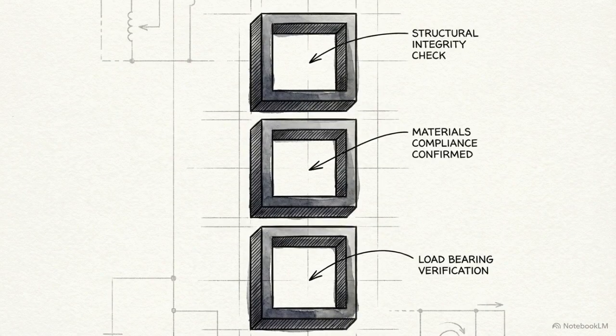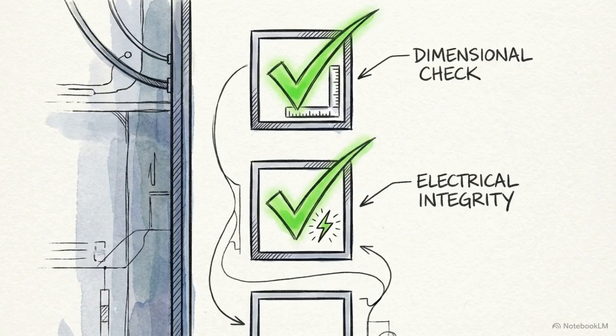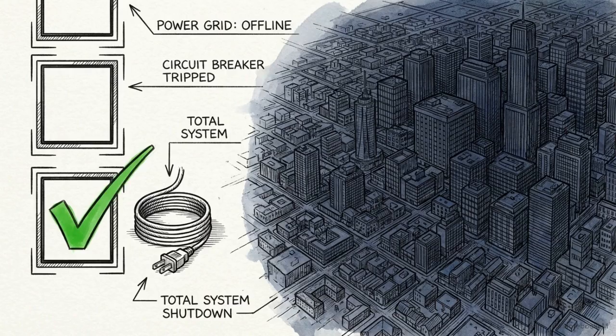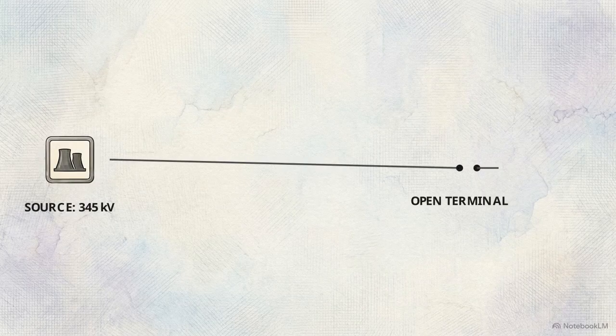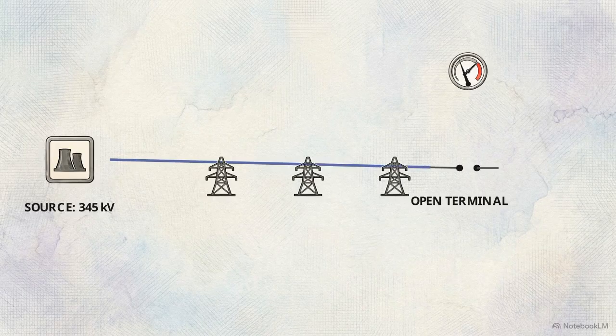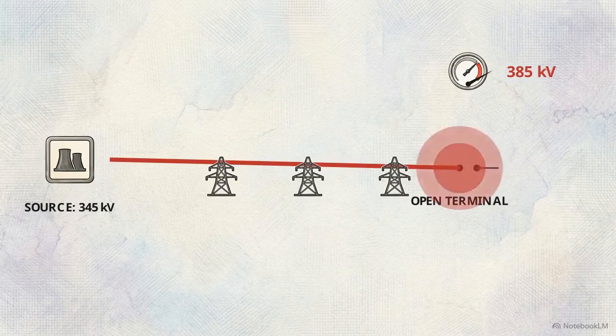For this phenomenon, known as the Ferranti Effect, to take hold, a transmission line needs three conditions. It must be long, it must be running at high voltage, and it must be experiencing an extremely light consumer load, or be completely open-circuited at the receiving end. This simplified schematic illustrates a perfect scenario. A grid operator is pushing a heavy 345 kilovolt signal down a straight 200-mile transmission vector. By the time that signal reaches the open terminal at the end of the line, it spikes to 385 kilovolts.